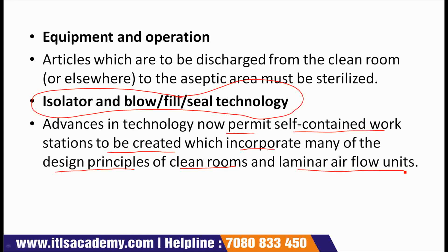Isolators are designed to minimize direct human interventions in processing areas by internally providing grade A positive pressure laminar airflow, and transfer devices accessed by means of a glove or sleeve system.